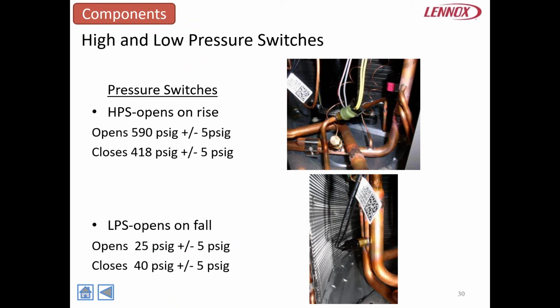So outside of that, we have our pressure switches here, high and low pressure switch, and we do have a 5-strike lockout on our boards. What that means is if we hit any of these pressure switches, whether it be high or low, 5 times in a given cycle, we're going to lock it out. So if you get out to the job and this system's on lockout, and we're going to talk about what it looks like on the board in just a second, 590 psi is where it locks out. That's a lot of pressure.